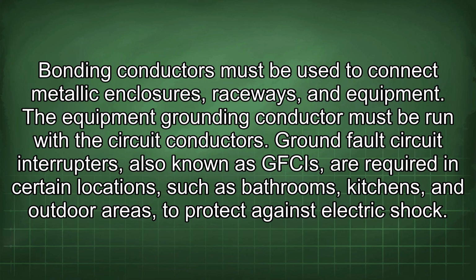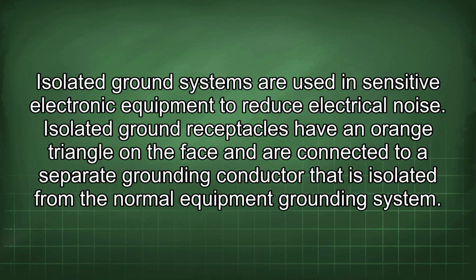Ground fault circuit interrupters, also known as GFCIs, are required in certain locations, such as bathrooms, kitchens, and outdoor areas, to protect against electric shock. Isolated ground systems are used in sensitive electronic equipment to reduce electrical noise. Isolated ground receptacles have an orange triangle on the face and are connected to a separate grounding conductor that is isolated from the normal equipment grounding system.